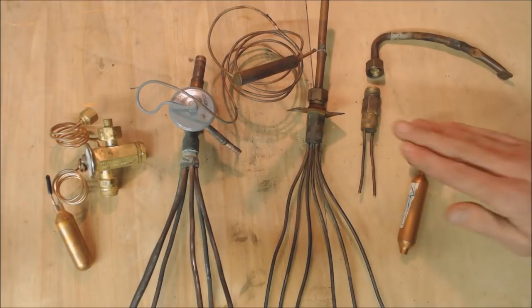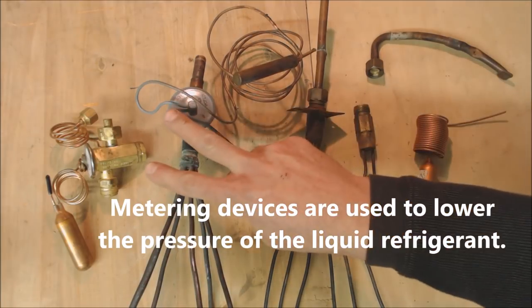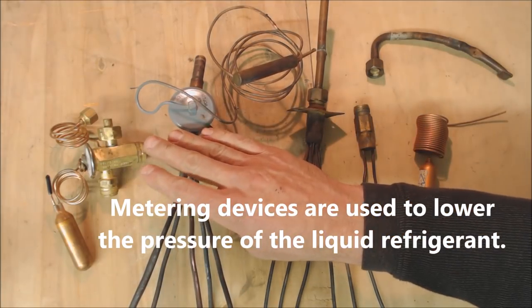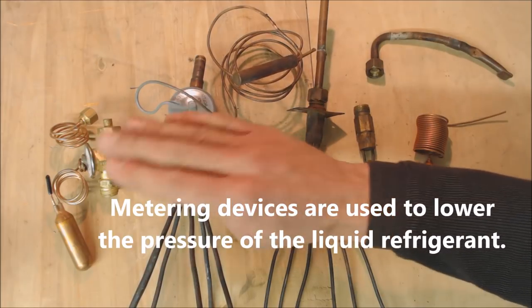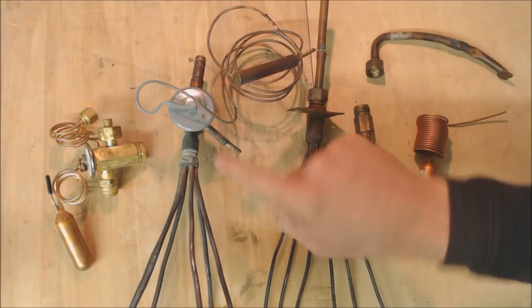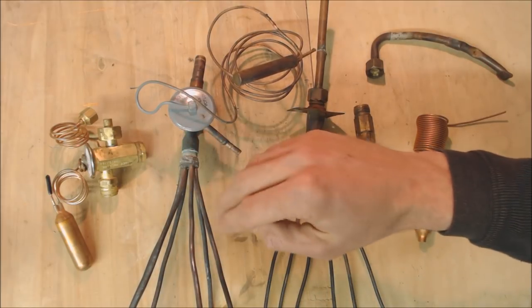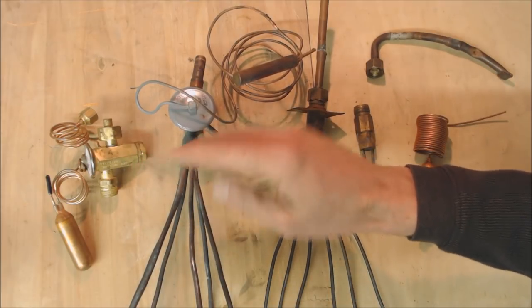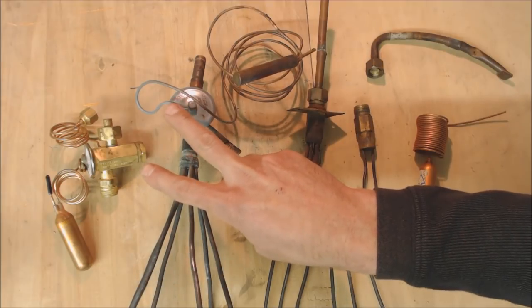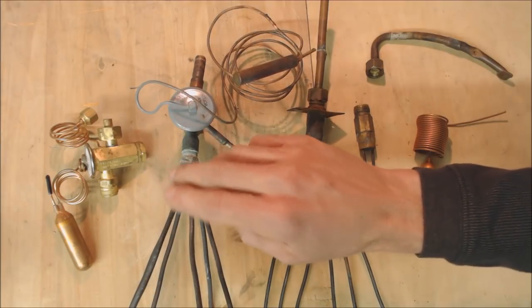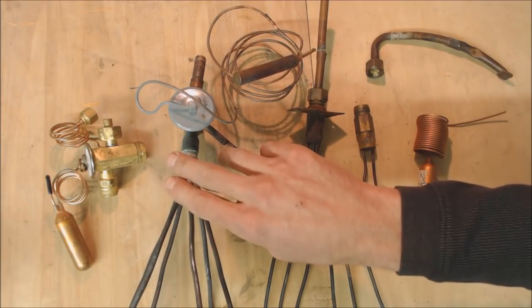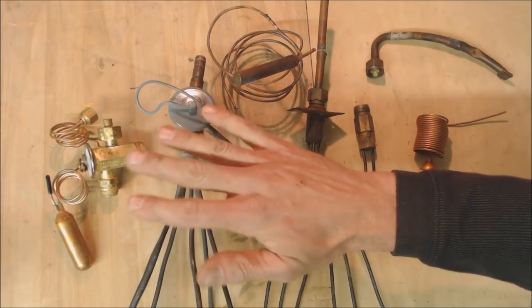Here we have three samples of metering devices. These are thermostatic expansion valves, also referred to as TEV or TXV. The ones that have an adjuster on the bottom allow you to adjust the spring pressure, and you're typically going to find them in refrigeration. These two come out of air conditioning systems and they have non-adjustable springs in the bottom.